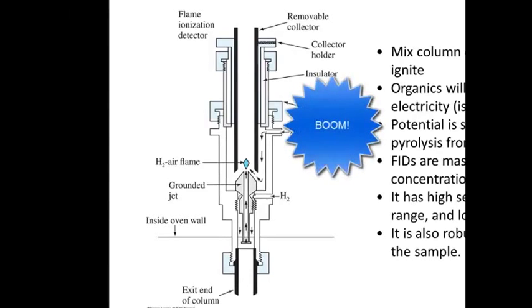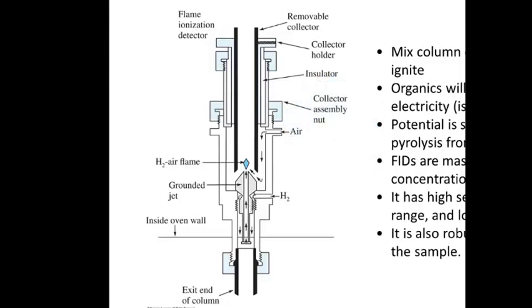I would say the workhorse of most GC systems out there today is the flame ionization detector. An FID, as it's also known, is a detector that takes what's coming off of the column and it mixes it with both hydrogen and air and then it ignites it. So it's basically a tiny little explosive device tacked onto your gas chromatography system.